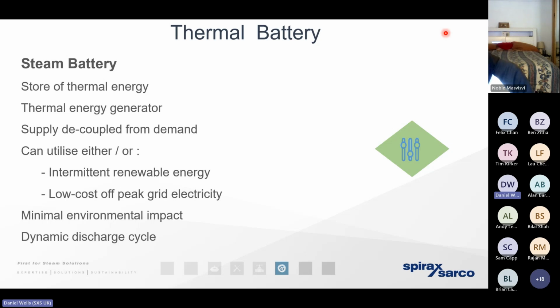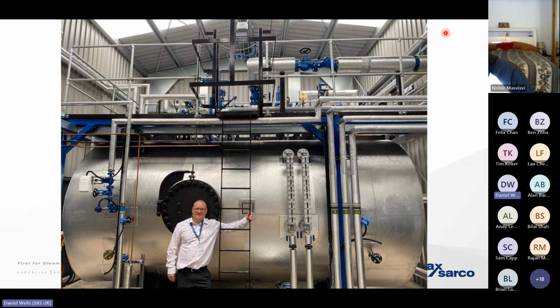We charge that vessel of hot water to 30 bar gauge, 225 degrees, and it sits there until such time that we need that energy. And we can achieve that energy simply by depressurizing the vessel.